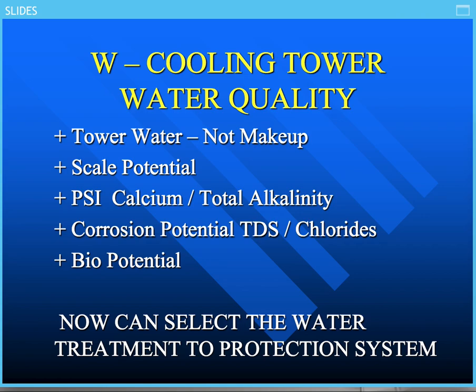If you want to carry 3 cycles, 5 cycles, 7 cycles, the thing you have to do is, okay, what was the water quality there, and what type of treatment do you need? Do I need acid to reduce the alkalinity? Can I use inhibitors that'll do that type of thing? So I need to identify what that scale potential is. If that scale potential is such that the calcium level and the alkalinity is too high, then you need to be able to modify your treatment program to be able to offset that.